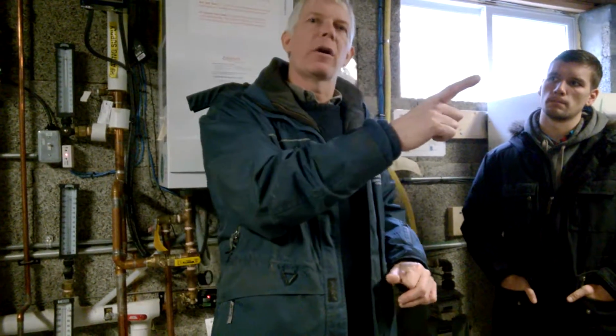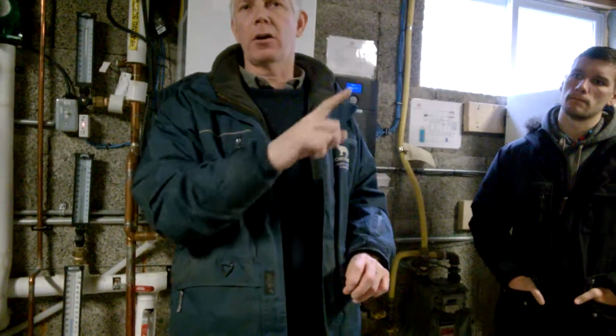And what is the COP during the minus 20, minus 25 on this system? At minus 25, that's where it approaches 1. The COP over the entire heating season is 3, and of course it actually runs up to 3.75. But there aren't really that many. I mean, we remember them, but there really are not that many minus 20, 25 degree nights. Most of them are minus 10, minus 15, where the COP is over 2, between 2 and 3. Oh, that's perfect.